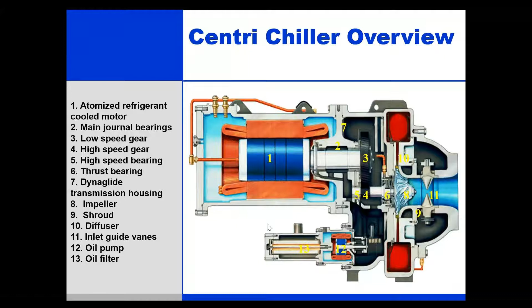So now we already discussed lift or head pressure, and we know how critical it is because a centrifugal is defined by its ability to generate lift or head. Now, why is it important? Because if it is not able to generate that lift and throw the refrigerant from the evaporator to the condenser, then the refrigerant will flow back. So lift is a very, very critical characteristic when it comes to a centrifugal chiller.